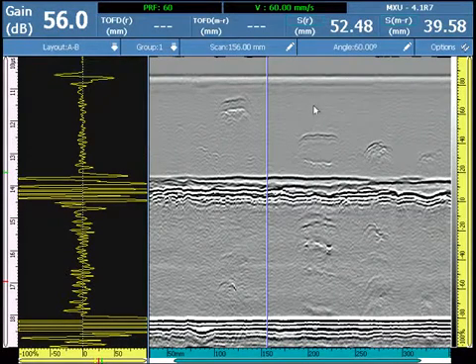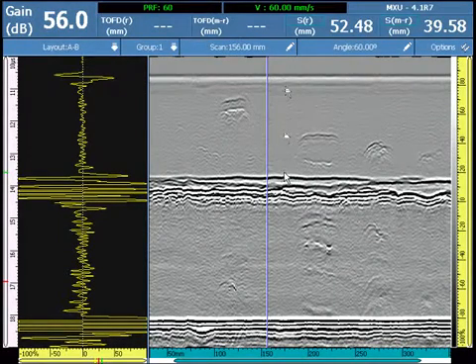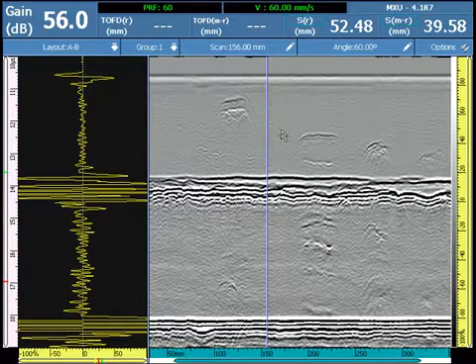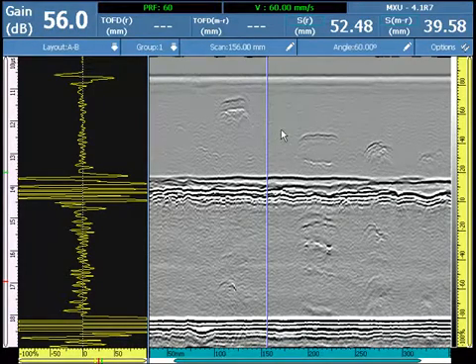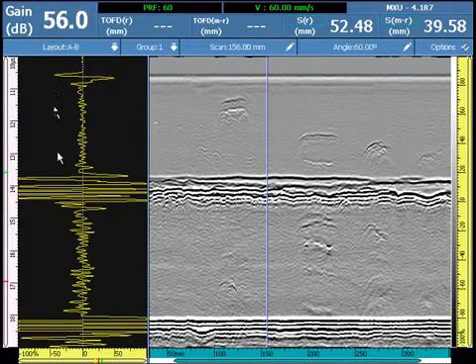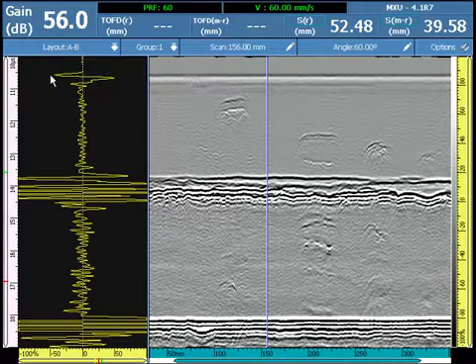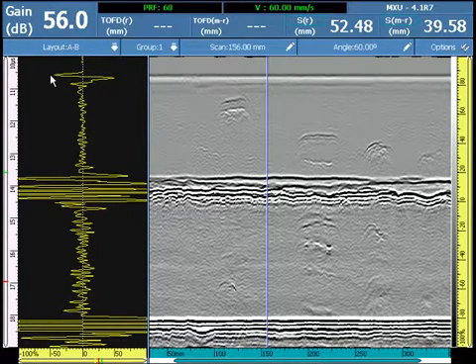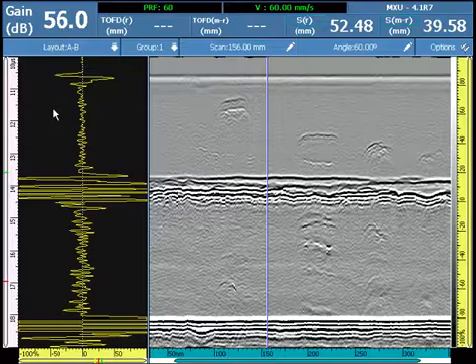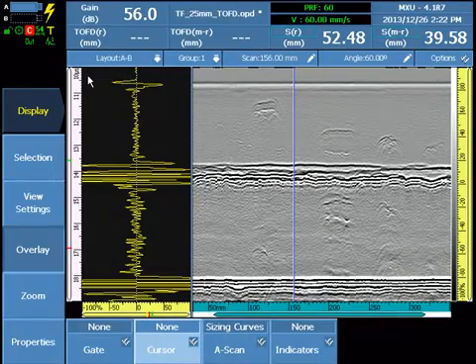The wedge delay and velocity calibration option for TOF data is the least used of the options and is typically beneficial for validating the position of the selected indication on the A-scan is as intended, based on a return velocity being near what was expected.